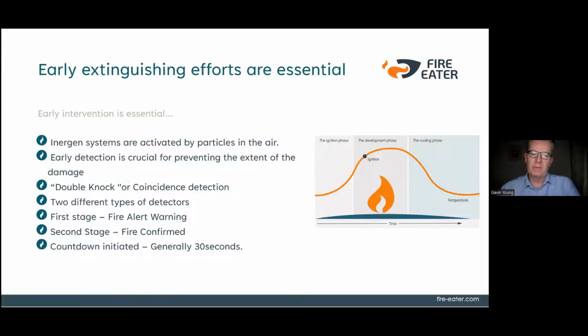Like if it's a wood fire, it'll be an optical sensor. If it's a smoldering electrical fire, it'll be an ionization type sensor. So there's two different types of detector. Detector number one will activate and you get what's called a first stage alarm. It's basically an alert to warn people within the room to evacuate. And then if a second detector activates, that's the second stage: fire confirmed, and a countdown is initiated. Generally it's around 30 seconds, depending on the size of the risk, to discharge. They're all the same. Inergen and the halocarbons all use this type of principle.